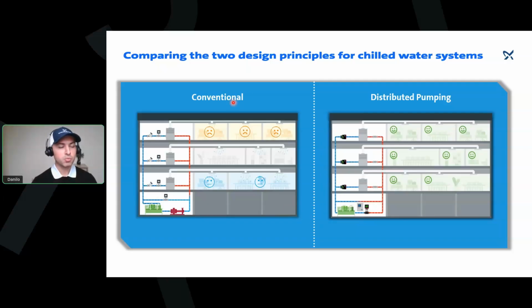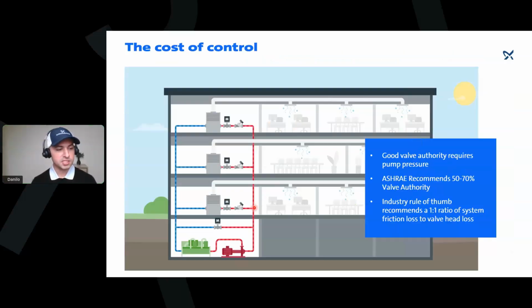So this is what we will call the distributed pumping system in essence, right? So again, as I mentioned, we want to reduce valve authority. Here in the United States, ASHRAE recommends the valve authority to be from 50 to 70%. You want to reduce that. The more valve authority, the more energy consumption, the more head you're creating in your system. And then your system needs to overcome that friction loss.